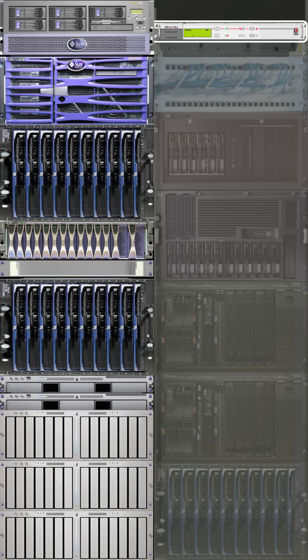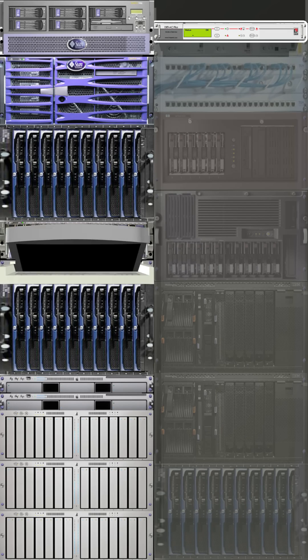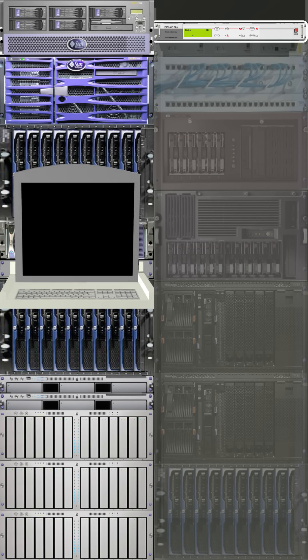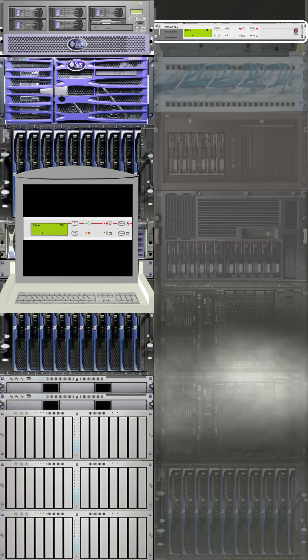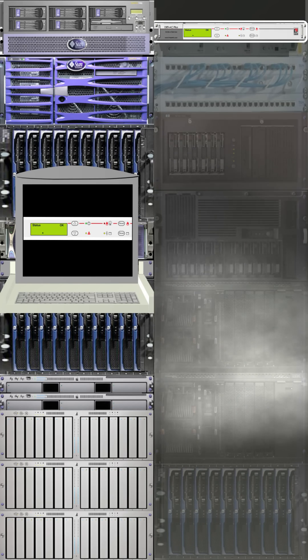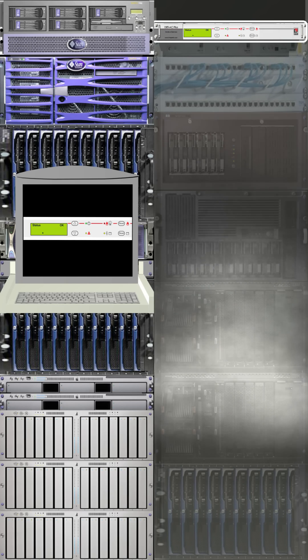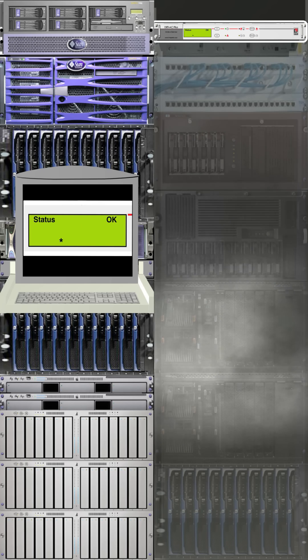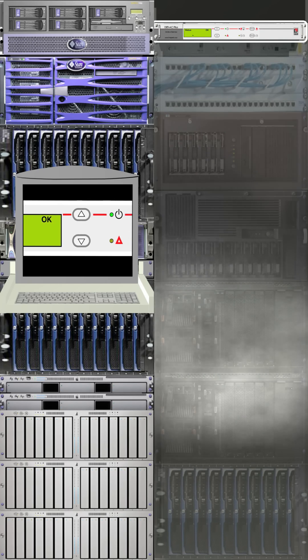The DETAC Plus from Rittal is a 1U fire protection system that mounts into a standard Rittal IP55 enclosure. The DETAC Plus detects smoke by drawing in the exhaust air of the active equipment within the rack. Utilizing two highly sensitive optical sensors, they can detect minute particles of smoke even in the early stages of a fire, the pyrolysis phase.